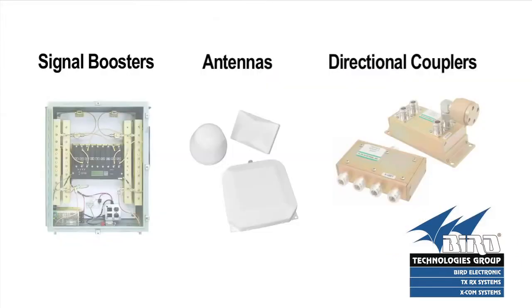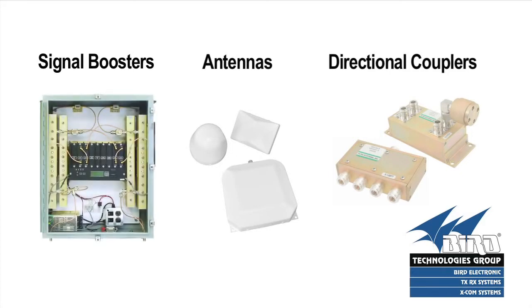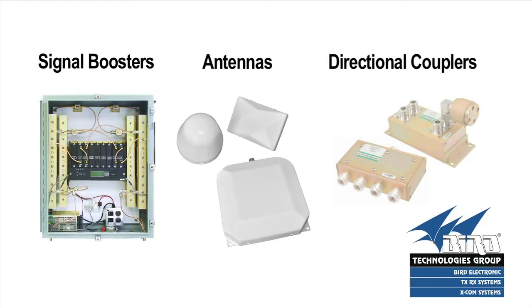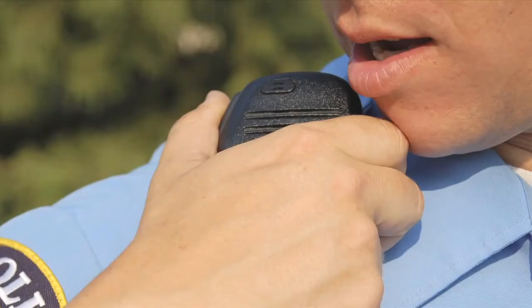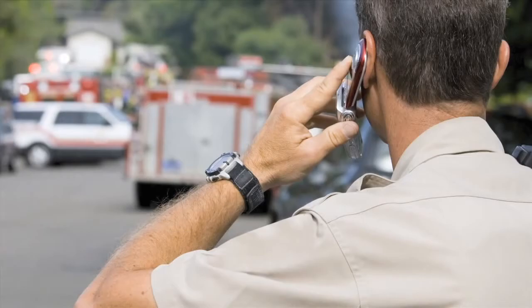As shown in these photos, a typical in-building DAS consists of three major elements: a bi-directional signal booster to relay and amplify RF signals to and from a remote base station, a network of antennas in the required coverage area, plus signal splitters or directional couplers connected by coax cables between the signal booster and the antennas. The antenna transmitted signals can then be picked up on portable radios for building owners and/or safety personnel.